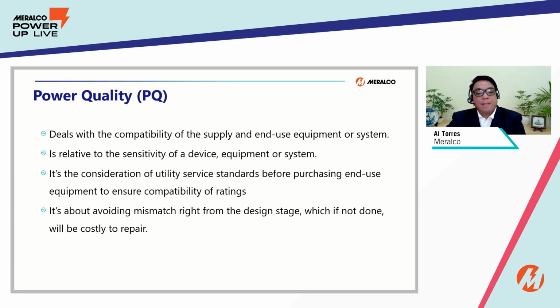So power quality is also relative to the sensitivity of a device, equipment, or system. Take note that we can still experience power quality problems even though all PQ parameters are within acceptable standard limits, especially if we are using mismatched equipment. That's why it is very important for the customer to consider the utility service standard before purchasing end-use equipment. Typical examples are the use of a 50 hertz motor. We all know here in the Philippines that the standard frequency is 60 hertz, so it will be prone to power quality problems. No? And using 380 volts rated equipment in a 400 volts nominal system voltage.